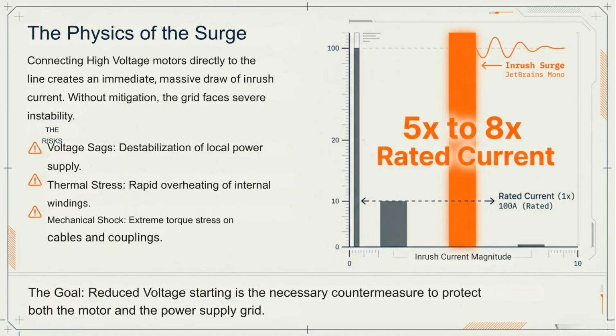Connecting high-voltage motors directly to the line causes an immediate, massive draw of inrush current, typically 5 to 8 times the rated current. This surge risks voltage sags, thermal stress, and mechanical shock. The goal is to use reduced voltage starting to protect both the motor and the power supply grid.